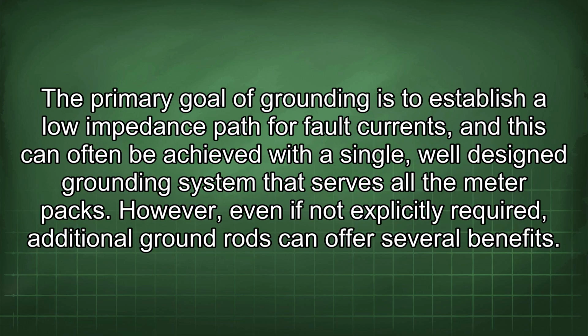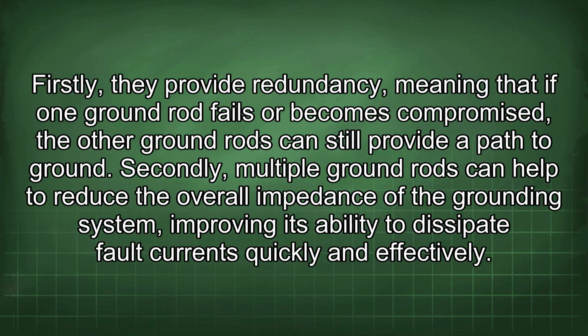The primary goal of grounding is to establish a low impedance path for fault currents, and this can often be achieved with a single, well-designed grounding system that serves all the meter packs. However, even if not explicitly required, additional ground rods can offer several benefits. Firstly, they provide redundancy, meaning that if one ground rod fails or becomes compromised, the other ground rods can still provide a path to ground. Secondly, multiple ground rods can help to reduce the overall impedance of the grounding system, improving its ability to dissipate fault currents quickly and effectively.